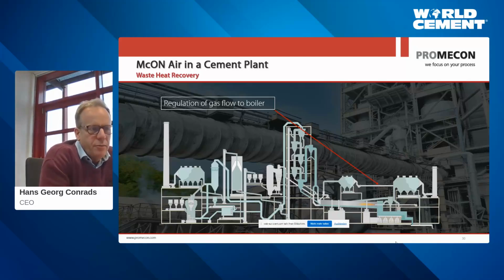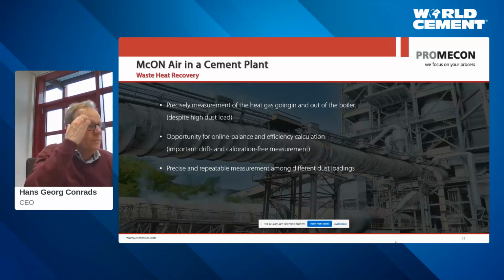And our measurements have been retrofitted to quite a few plants, especially when they add a waste heat recovery system. So if you are adding something to your plant and the manufacturer of the waste heat recovery system tells you, I can't measure your gas flow, you tell them, yes, you can, because we have quite a few examples and references that show our waste heat recovery measurements. So you can measure the gas that's going into the boiler and out of the boiler. You can do, of course, a measurement of the temperature of the gas and the temperature loss. And that will then, of course, give you a mass and the possibility for a good mass energy balance.